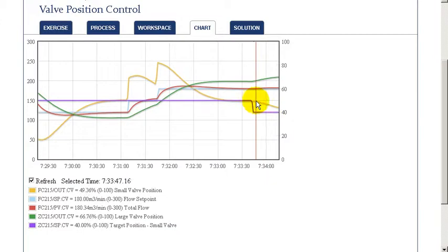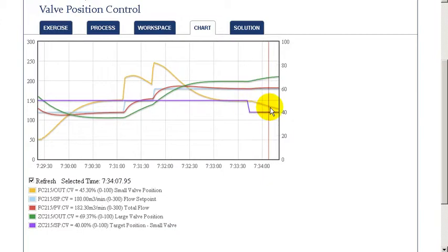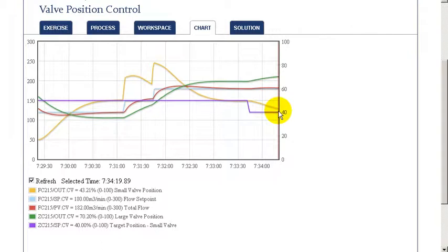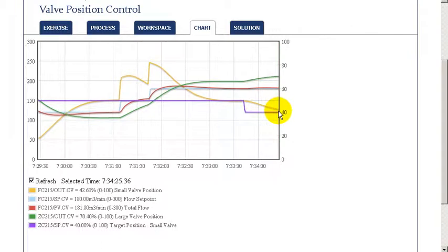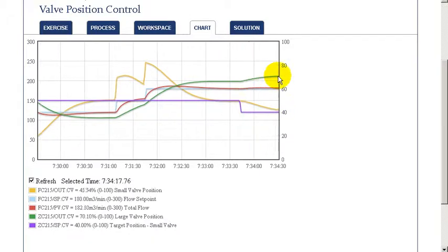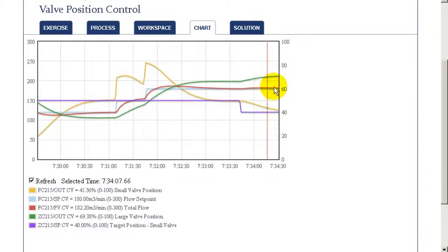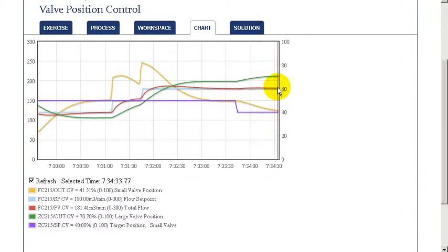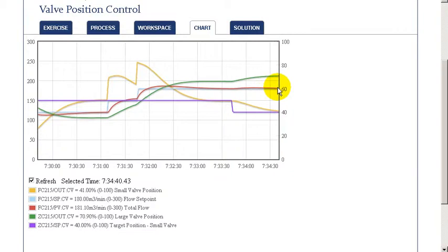The larger valve makes up for any change in flow by gradually changing. So, through this combination, we're able to achieve our target flow and also to be able to achieve a position for a smaller valve that allows it the freedom to take changes both increase and decrease in a very fast manner.